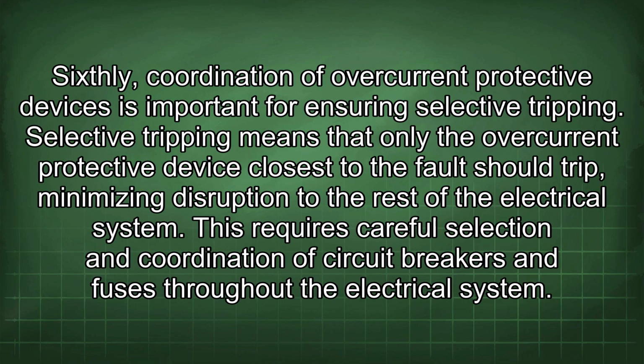Sixthly, coordination of overcurrent protective devices is important for ensuring selective tripping. Selective tripping means that only the overcurrent protective device closest to the fault should trip, minimizing disruption to the rest of the electrical system. This requires careful selection and coordination of circuit breakers and fuses throughout the electrical system.